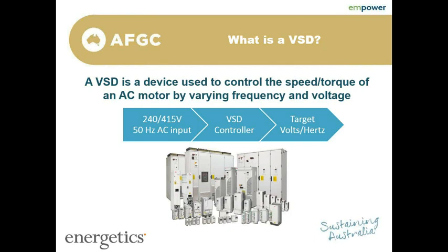There's a few different types of VSD controllers. The most common are pulse width modulation VSD controllers. They take the AC voltage and convert that through some electronics. So there's a diode bridge and capacitors. Then that goes through to a DC bus voltage, and then the inverters bring it back to an AC signal, a near sine wave, and that's adjusted to whatever the application requires. I won't go into too much more detail around that, but effectively that's a very high-level overview of the process of VSDs.